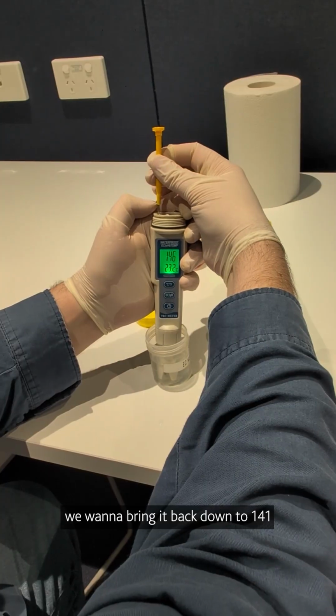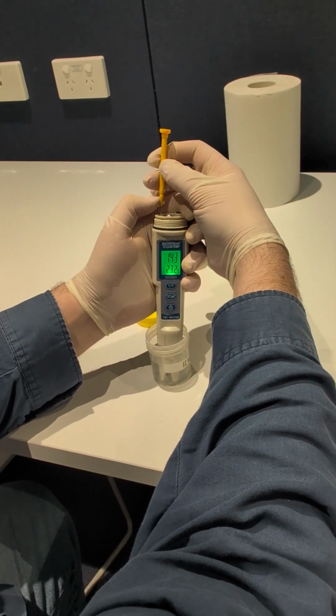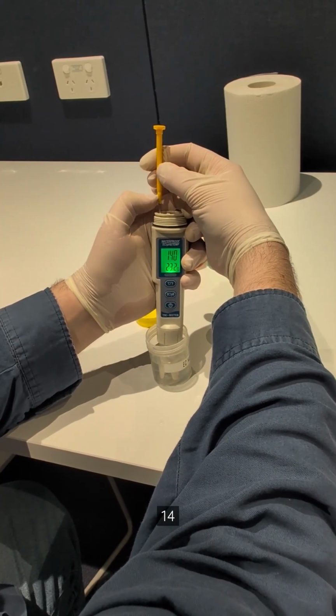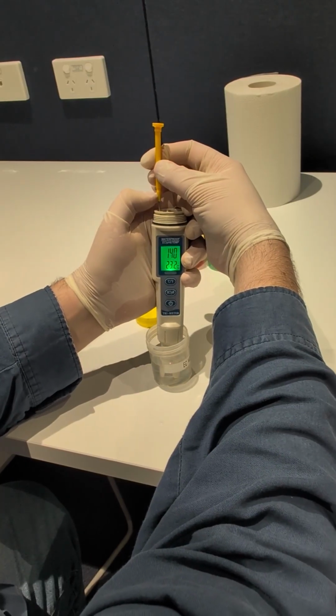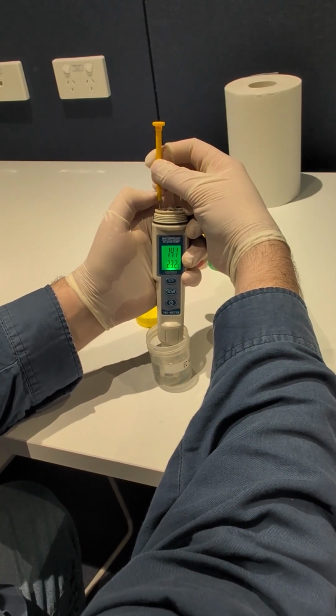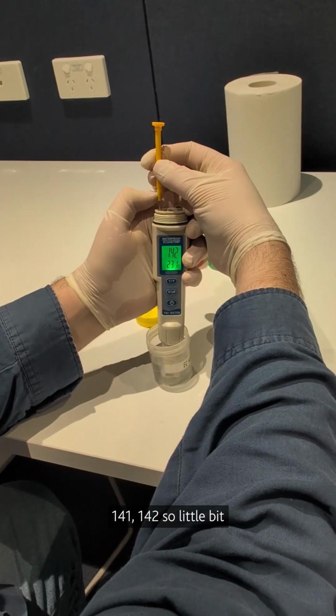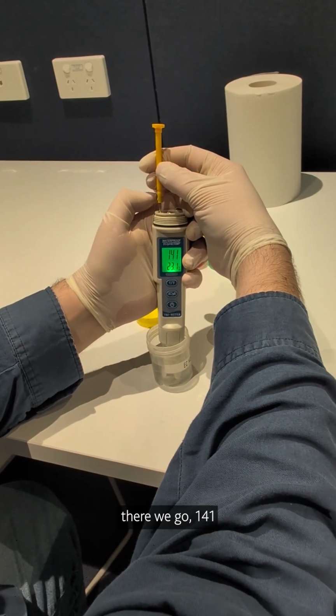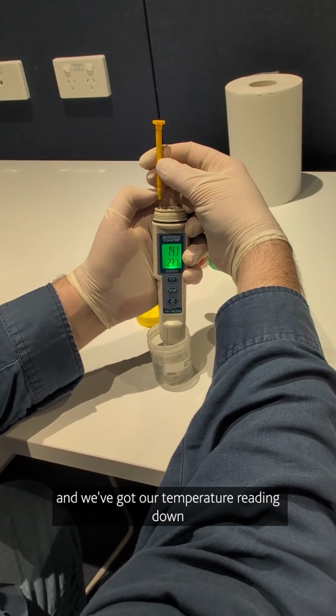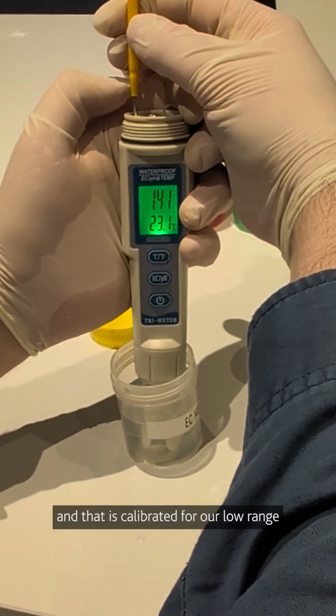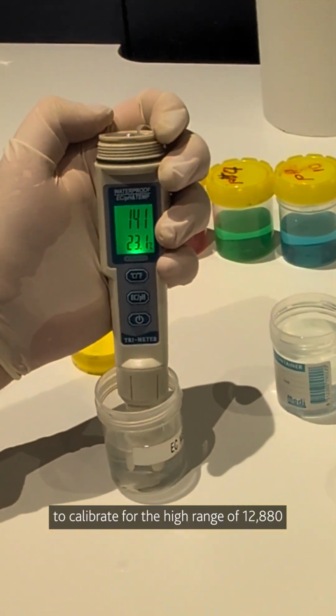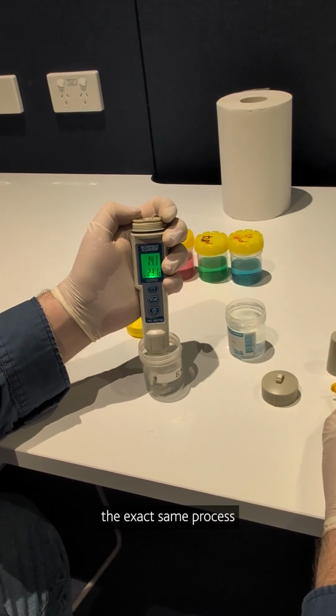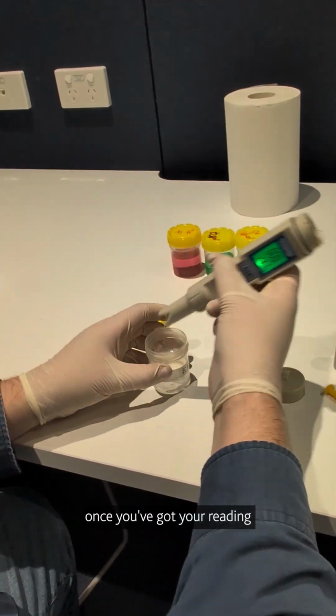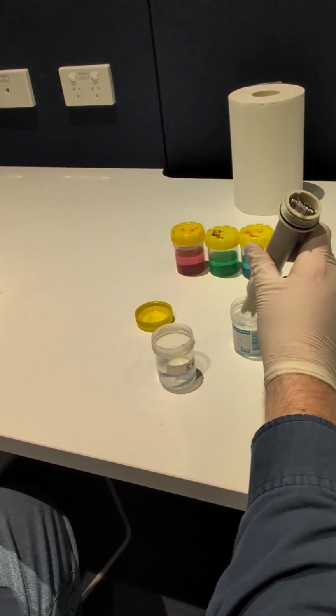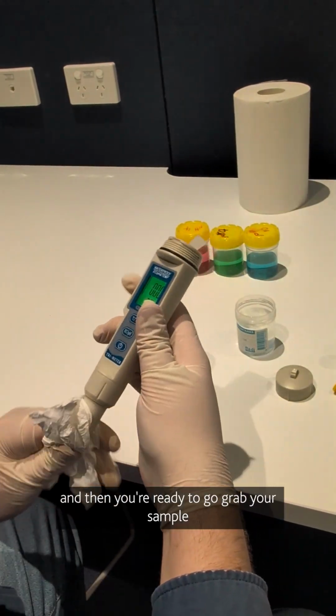We want to bring it back down to 141. 141, 142. So a little bit, there we go, 141. And we've got our temperature reading down the bottom as well. And that is calibrated for our low range. To calibrate for the high range, so the 12,880, the exact same process, and same way, just with the screwdriver on the top. Once you've got your reading, you can give it a rinse in the distilled water, dry it off, and then you're ready to go to grab your sample.